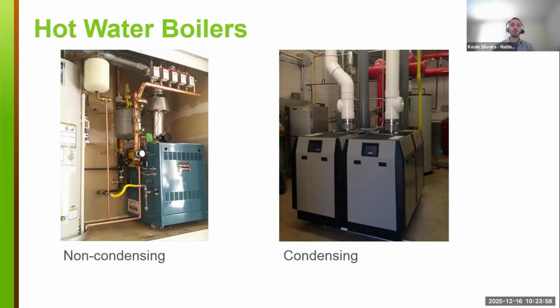distribution systems with them, which could make it easier for a partial or full electrification opportunity. Condensing boilers are much more efficient than the non-condensing options. Just a good understanding of what those systems are. These hot water boilers can provide heat to air handlers, rooftop units, baseboards, a lot of different distribution systems that could be connected to these systems. And there are different strategies we could look at when we are replacing them or partially displacing them. For our programs, we can always leave those systems in place for backup. Just one thought to have.